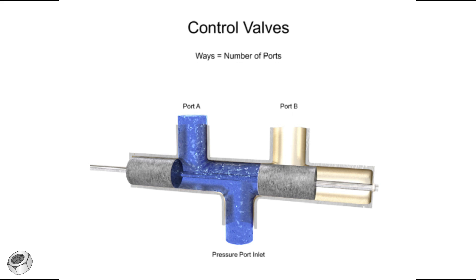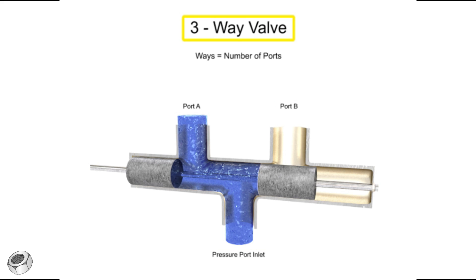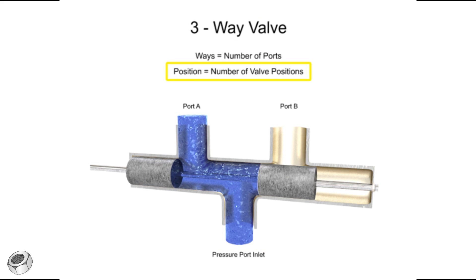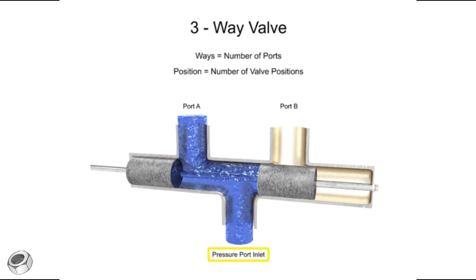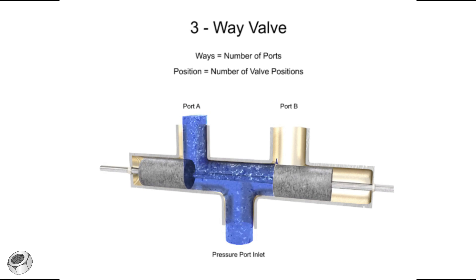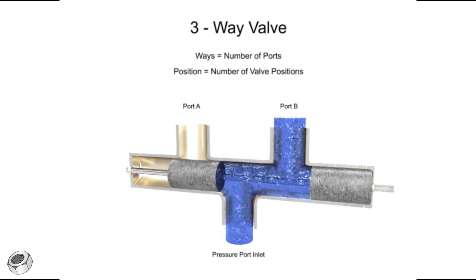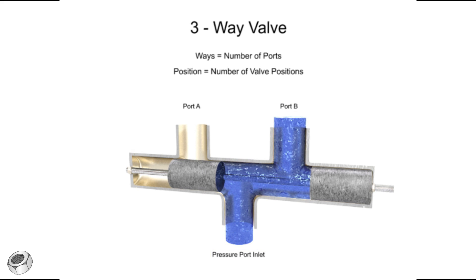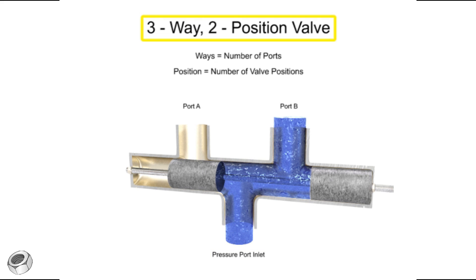This valve has three ports, so it is a three-way valve. The term position refers to the number of discrete operating positions of the internal valve element. For this spool valve, one position allows fluid to flow from the inlet to port A, and a second position allows fluid to flow from the inlet to port B. Therefore, this is a two-position valve.